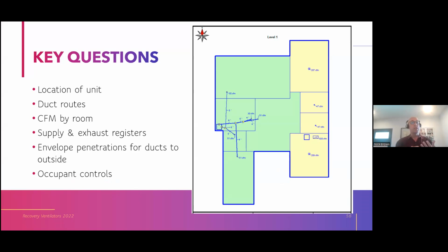Where's the unit physically going to be located in a way that's serviceable, in a way that's adjacent to all the spaces you need to ventilate? What are the routes for the ducts you can take? What are the CFM you need by room? Now, you don't have to define CFM by room when you specify the unit, but by the time they install it, they do, right? And duct routes and location, I would argue, are some things you do need to think about before you specify them on the project.